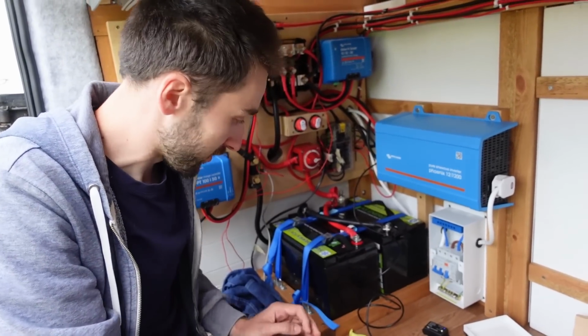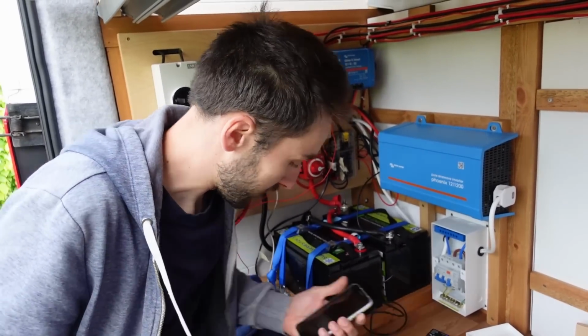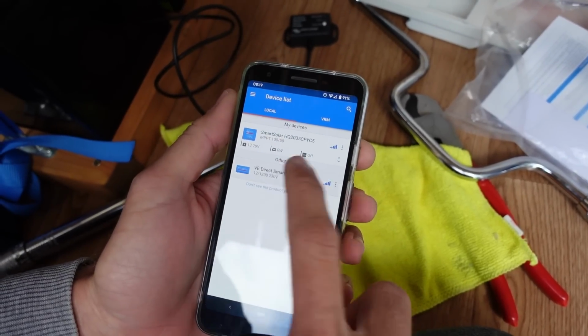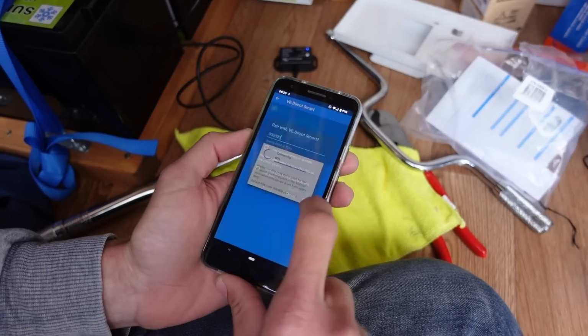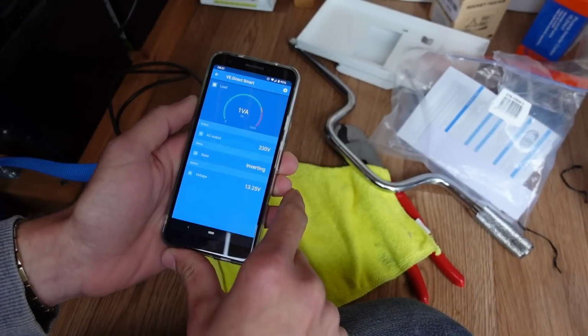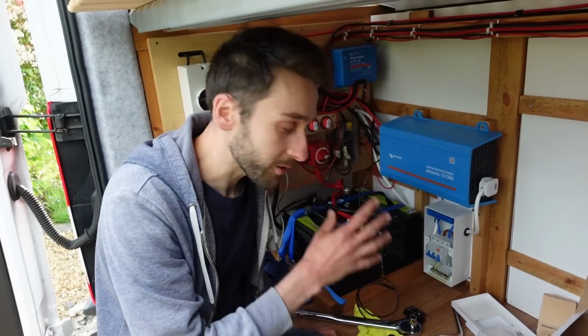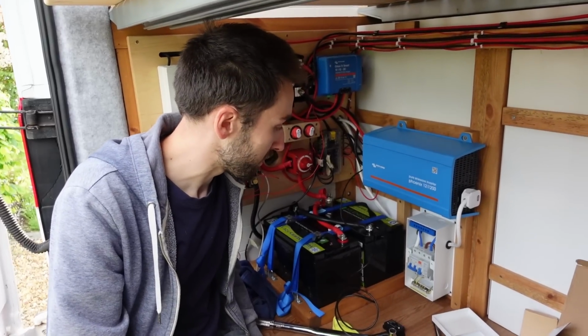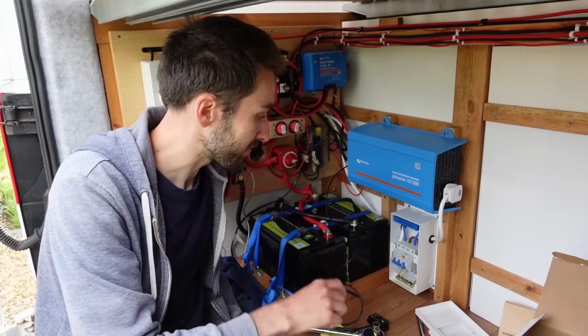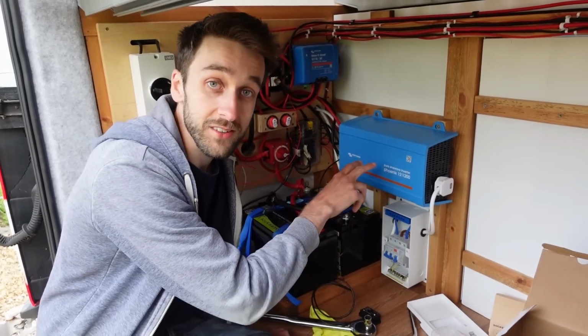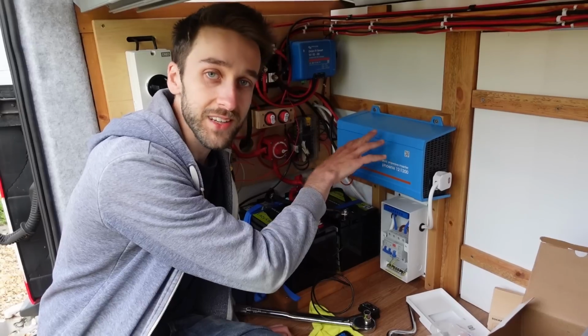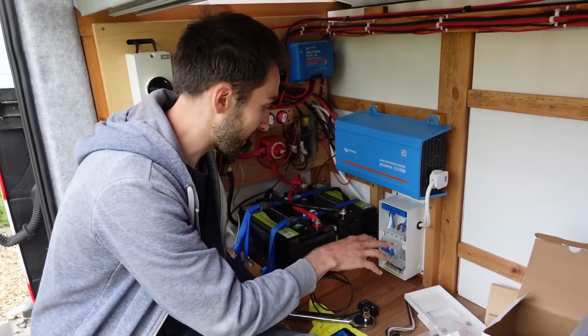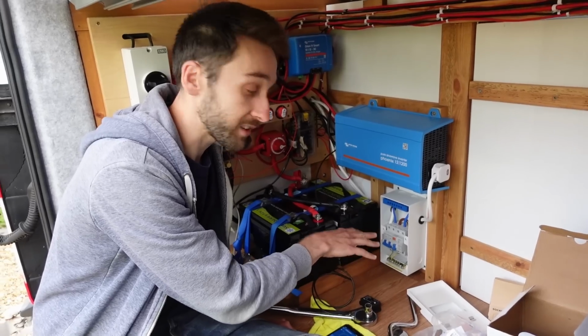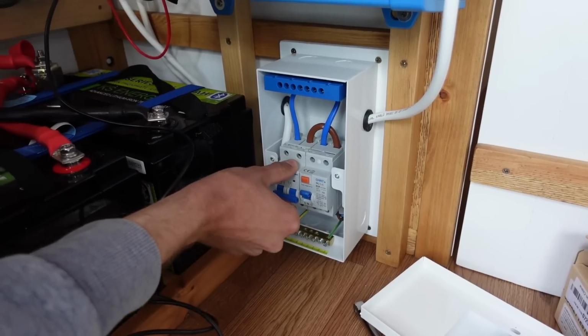So we should be able to see it in the app, if I can find my phone. Oh, there we go. New device. There we go. It's basically set up, and in theory you can plug stuff into the sockets and actually have them work. But before we do that, we want to just check that the RCD is working correctly. At the moment we haven't actually changed the neutral earth bond inside. So what we're expecting is that the RCD shouldn't be functioning yet because it doesn't have that bond.